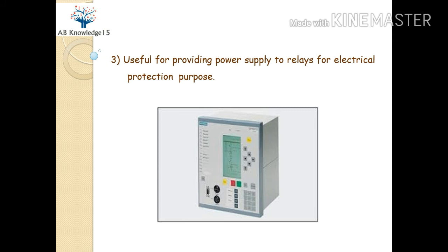The third use is providing power supply to relays for electrical protection purposes. DC power supply is used here because in case AC power supply fails, power must still be available for protection purposes — including under-voltage and under-frequency protections. The relay power supply is generally provided in normal conditions from battery chargers, which are supplied from AC power. In case AC power fails, the battery bank comes into line and provides power supply to these numerical relays.